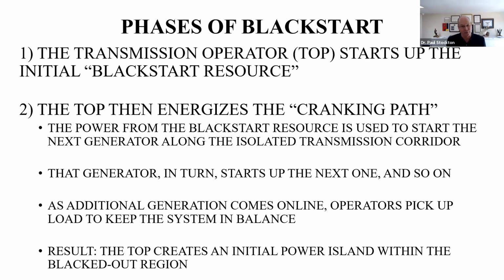Once that Black Start resource is energized, we send that power down what's called the cranking path - an isolated transmission corridor connected to special Black Start generators along the path. You use that additional power to start up the next generator along the cranking path, then with that additional power you start the next one, and so on down the path.